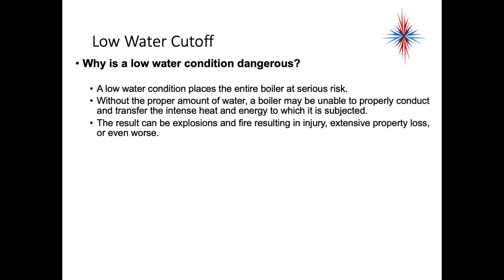Now if a low water condition has happened and you come upon a boiler that is hot and empty, or a boiler that has cut off on low water, do not just open the water feed valve. You want to shut it off and allow the boiler to cool all the way through, and then you add water. If you add water to a hot boiler, it will flash to steam as it comes in and it will blow that boiler up. Since you're standing right behind it adding water, you can get hurt, seriously hurt, or killed. Steam explosions are nothing to mess with.